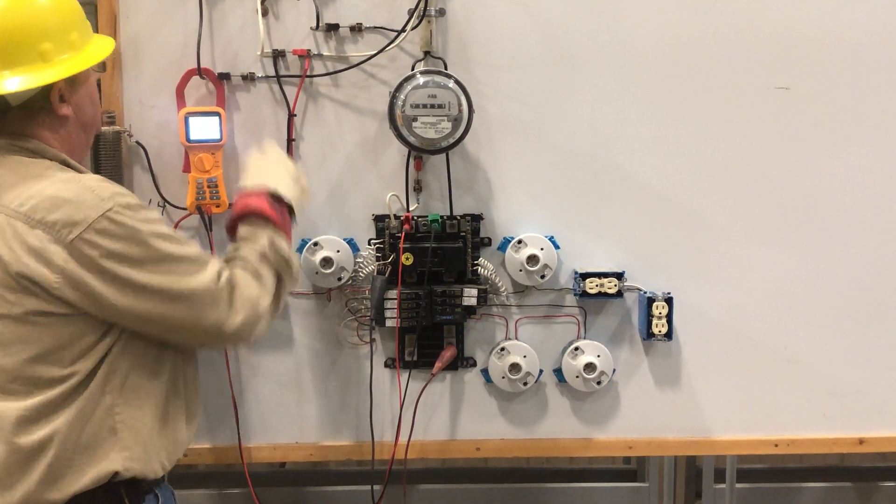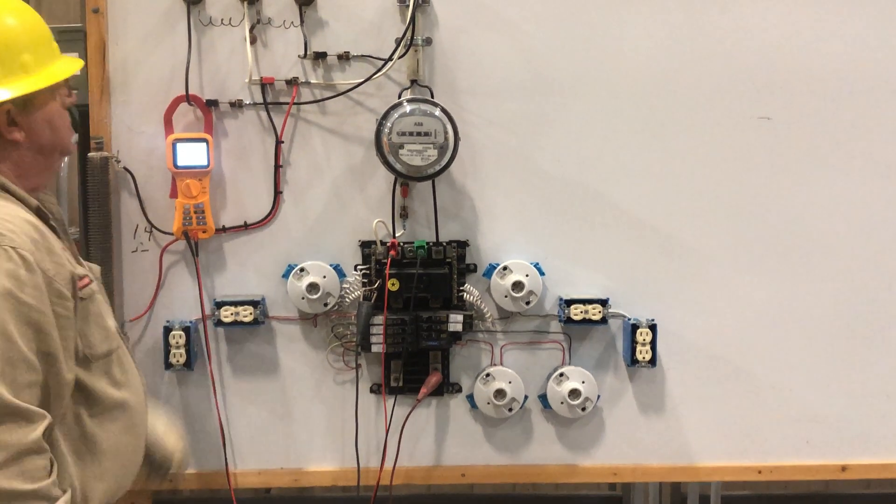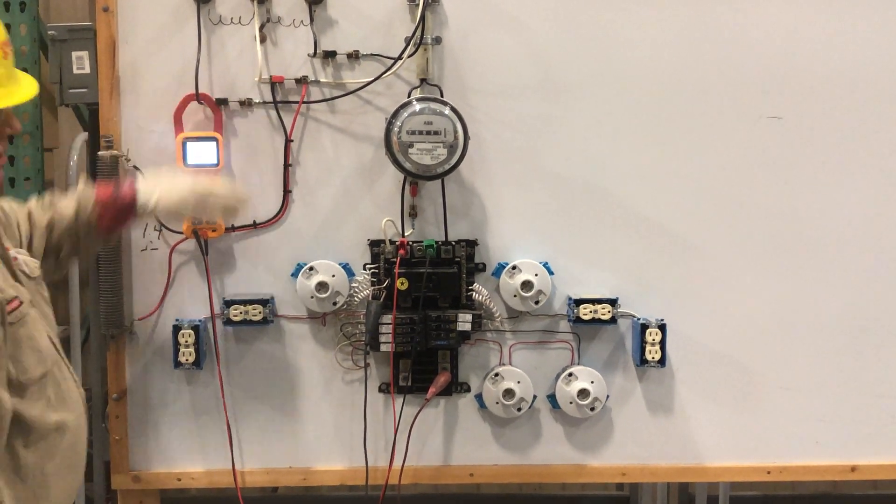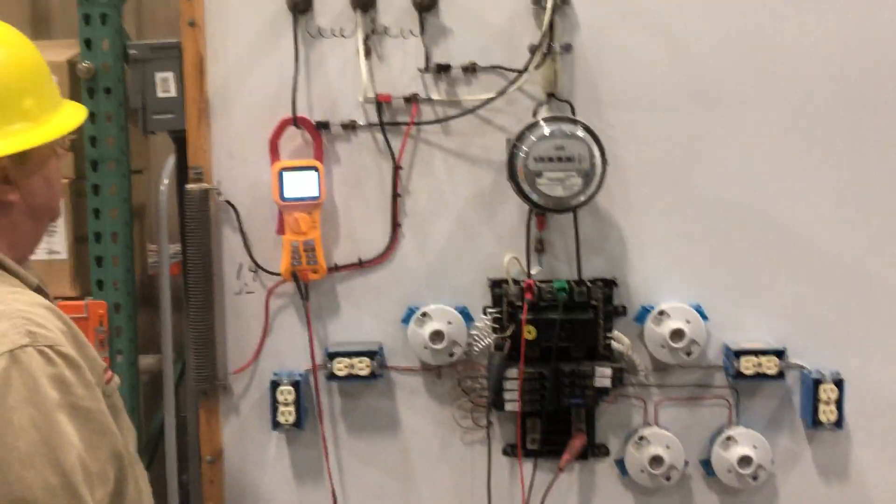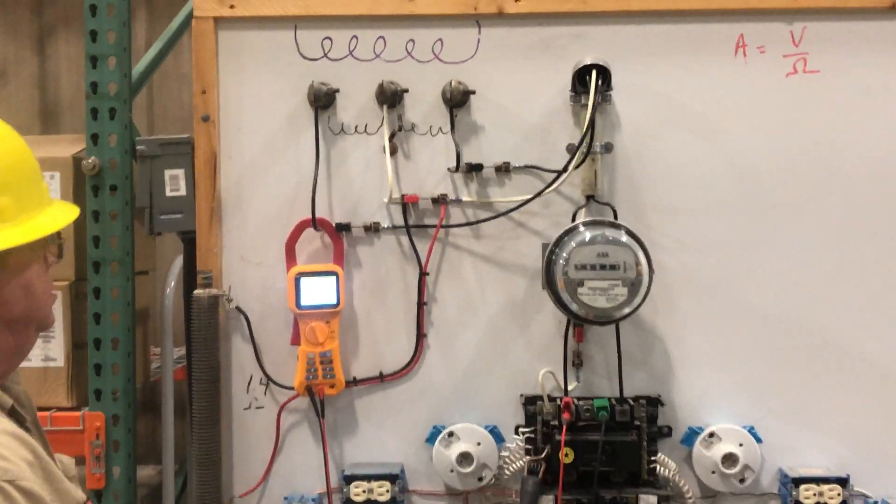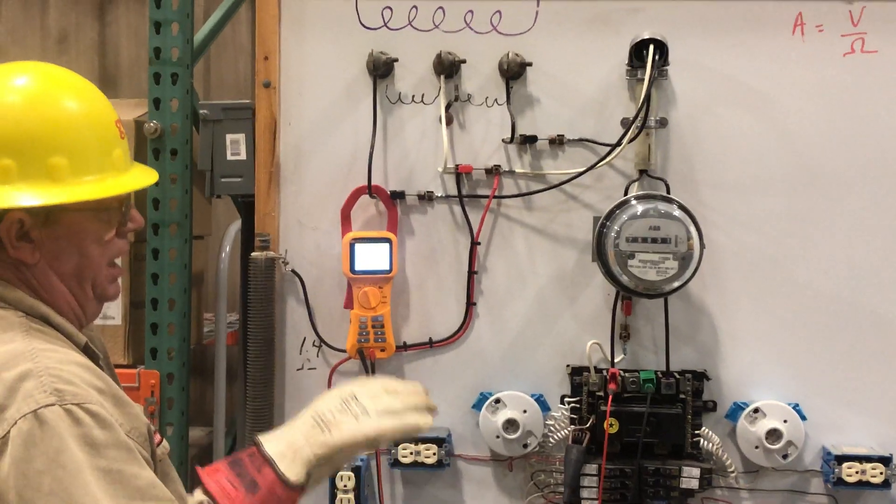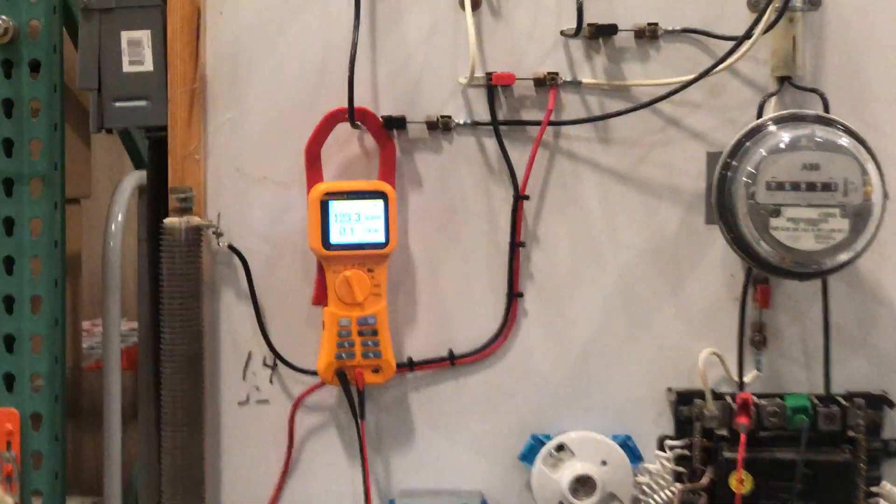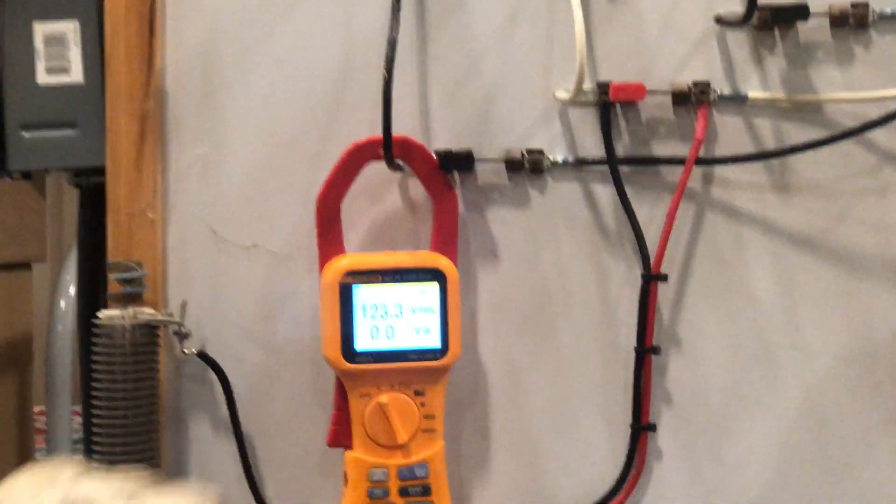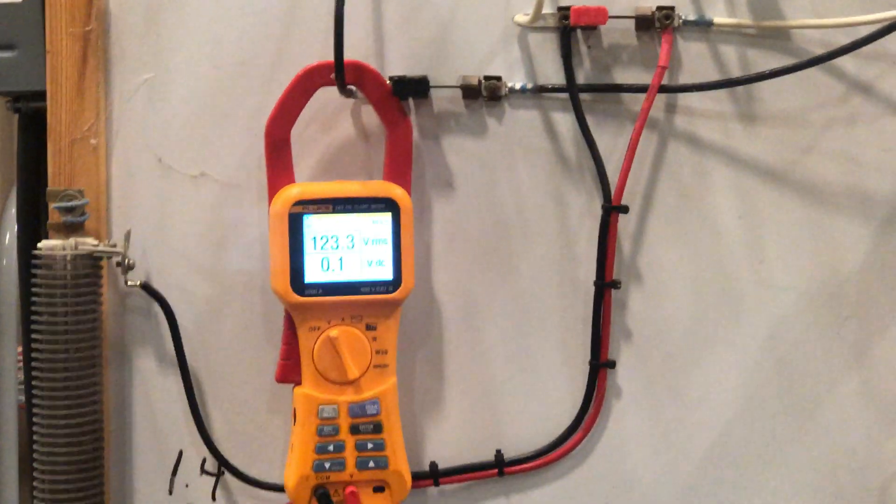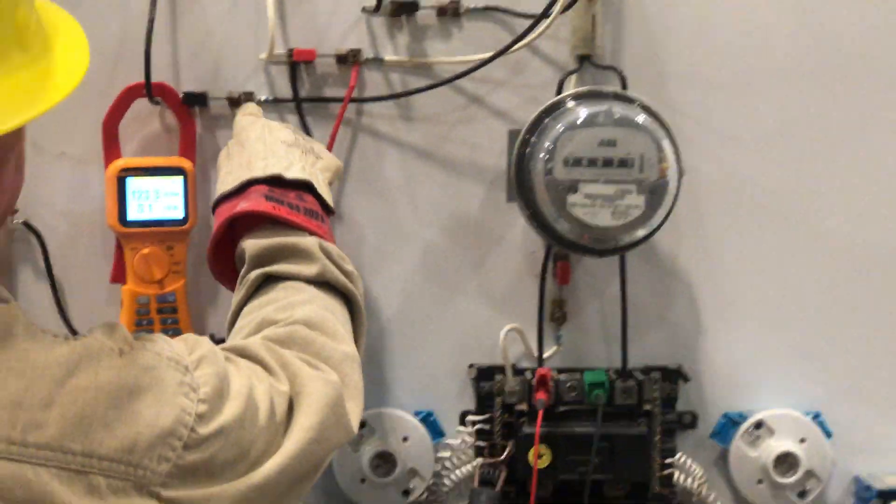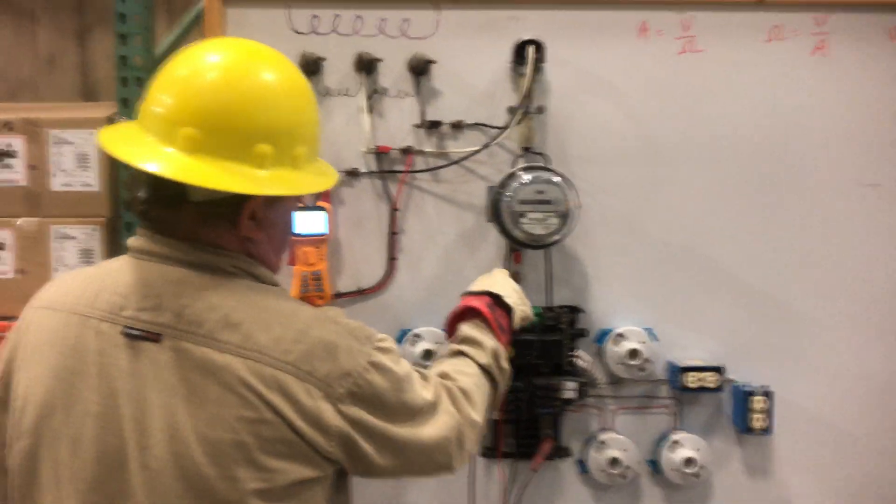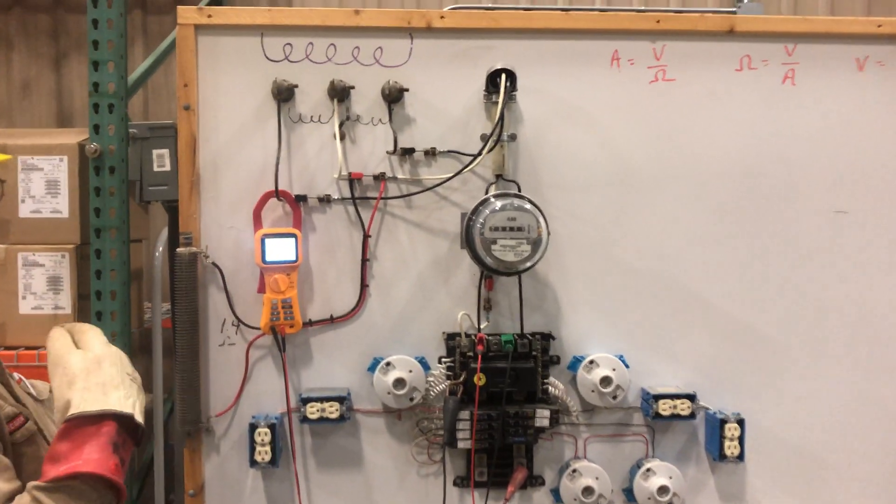Now I'm going to bring on load with the neutral closed. The neutral is in good condition. 121.6, 122.7. And you're watching the loaded leg or the unloaded leg, 123.3. Neutral is in good condition. We added 24 amps and we watched the unloaded leg go to 123.3.